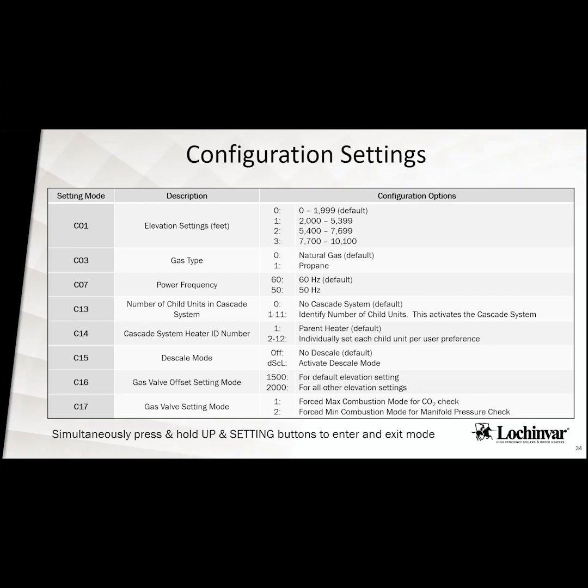And then that gas valve setting mode, you can actually force this unit, if you wanted to, into combustion mode for a CO2 check, or put it into minimum combustion for the manifold pressure check. So on the exhaust side of this, there is a port that you can pull off and put your analyzer in, coming straight off the top of that unit. So any questions on any of those settings?